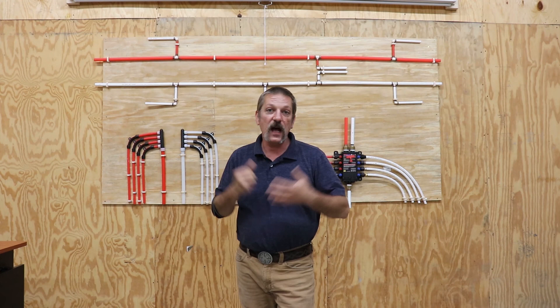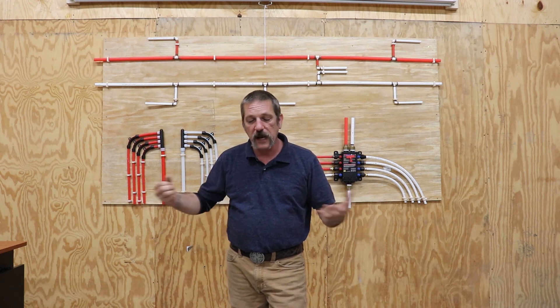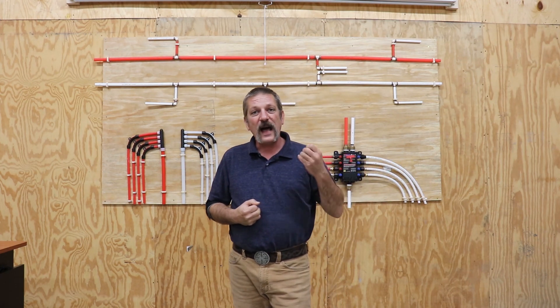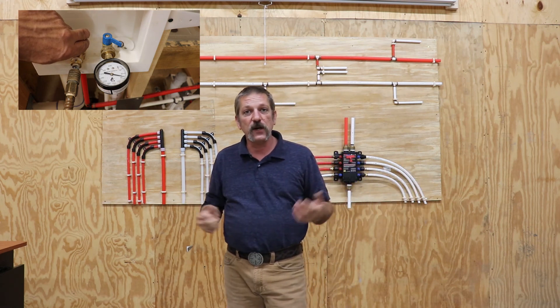So what's that mean for us as residential new construction plumbing? Why do we need a PRV? Why do we need a pressure regulator? It's because we test our plumbing at rough end on our waterline side at or above 100 psi to make sure none of our fittings blow off and that everything's good and we're not going to have any accidents later on.